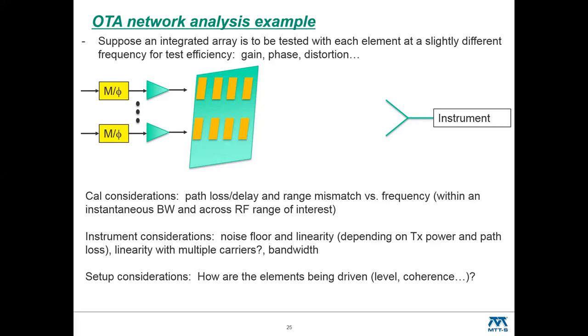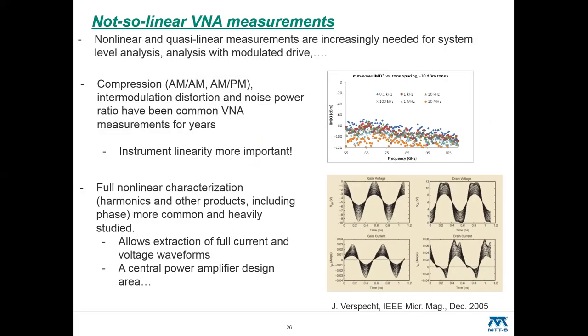That sort of leads us over into our little transition into the nonlinear measurements. We talked about the instrument linearity before, that isn't a surprise. But some trends, certainly at lower frequency, is full waveform acquisition, where particularly for maximum power amplifier efficiency, getting a particular waveform shape is critical.